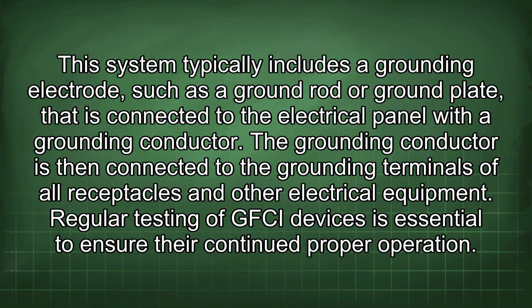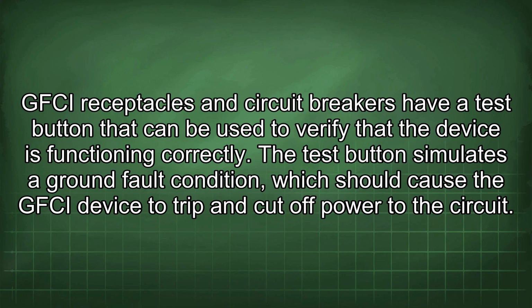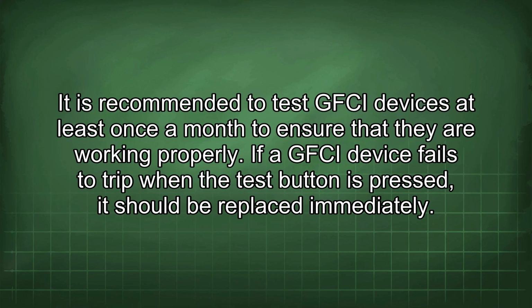Regular testing of GFCI devices is essential to ensure their continued proper operation. GFCI receptacles and circuit breakers have a test button that can be used to verify that the device is functioning correctly. The test button simulates a ground fault condition, which should cause the GFCI device to trip and cut off power to the circuit. It is recommended to test GFCI devices at least once a month to ensure that they are working properly.